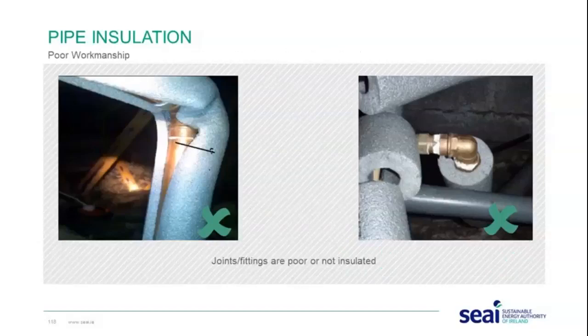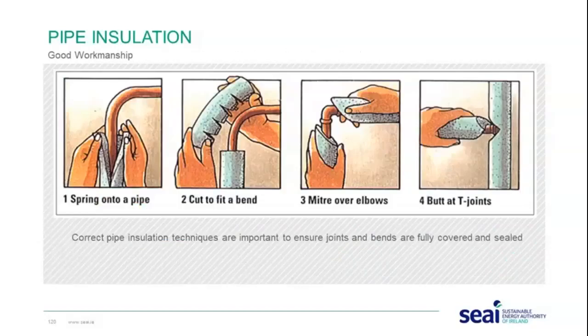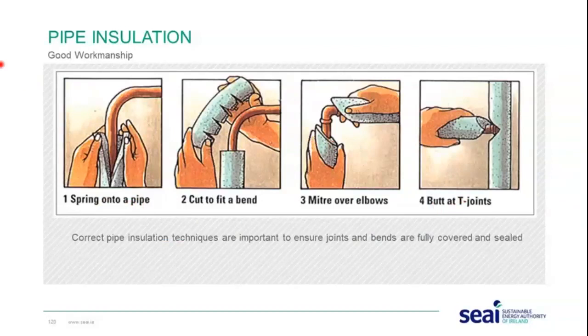Examples of poor workmanship include joint fittings that are not insulated — there is a real risk of freezing as it will be colder after insulation upgrades. Good workmanship means using correct pipe insulation techniques to ensure joints and bends are fully covered and sealed. The correct technique involves springing the insulation onto the pipe; on bends, you notch out, and on elbows you mitre and butt the joints together.